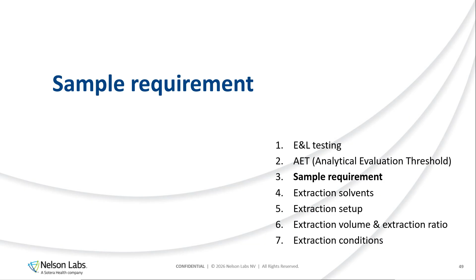First up, I want to explain a bit how sample requirements are calculated in general. This is done in 4 steps. First, you select the amount of solvents that you want to use, and then you can determine how many extractions you will do. Then we calculate all AETs. We've done one AET calculation now, but I will do it in more detail and explain a bit more on the LOD and the LOQ. And then we will determine all required volumes. And after that, we can apply the extraction ratio to determine the final sample requirement that is needed for an E&L study.